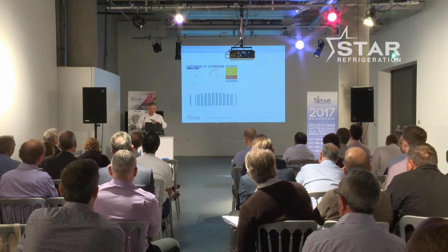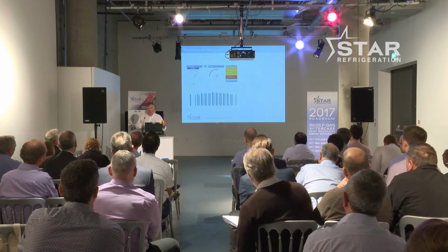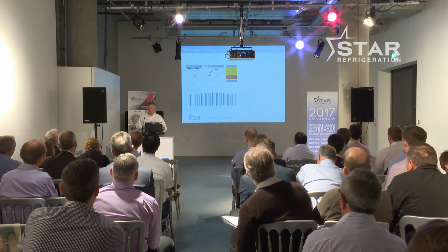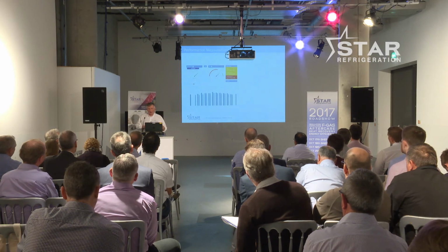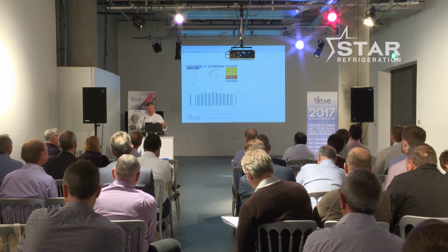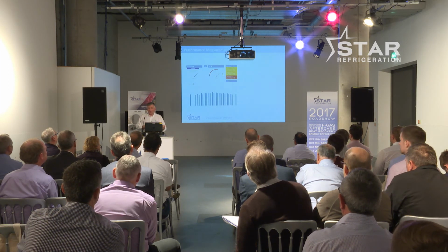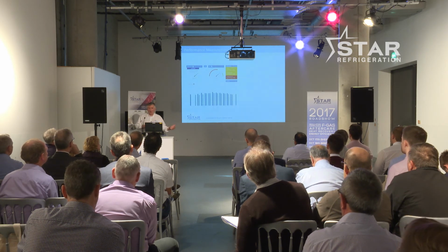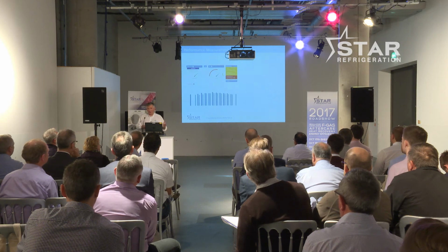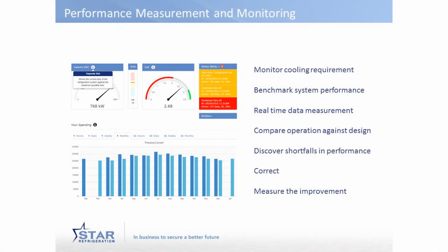On the Star booth at the back, you'll see a demonstration of a system that we call Ethos, which is a fairly new development, a method of measuring and then assessing operation of refrigeration systems. And it's designed to improve energy, but actually we found lots of other clever ways to use it. It's really interesting. In one case, a user was saying, I think I need to buy a second chiller because we're going to extend our production process and we don't have enough cooling capacity. And by installing an Ethos system, taking readings and looking at the way that they used their plant, we were able to say to them, actually you don't need a new chiller, you just need to reconfigure the existing system that you've got. So that not only saved them the energy cost of running a second chiller, which would have been substantial, it saved them the capital cost of buying the chiller and getting it installed, all for the sake of doing some measurement.